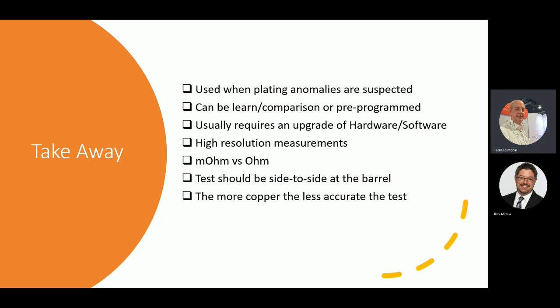Milliohms versus ohms. When we're doing side to side or barrel test, we want to be real close on the probes. But also when we're doing a barrel test, we want to be side to side, and we want to be as close as we can to the barrel annular rings if possible, because that provides the highest amount of accuracy.